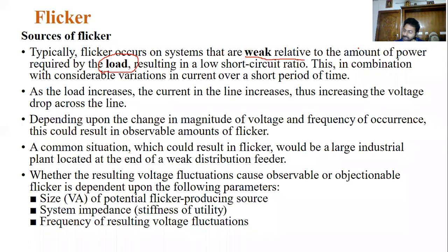Remember, we will get flickers not only by sudden load changes. That also leads to other problems, voltage sags and swells and other power quality issues. But especially, flickers occur because of electric arc furnaces, one of the main reasons, and another one is large motor starting. You know that large motor starting leads to voltage dips, but it also causes flickers in the system.